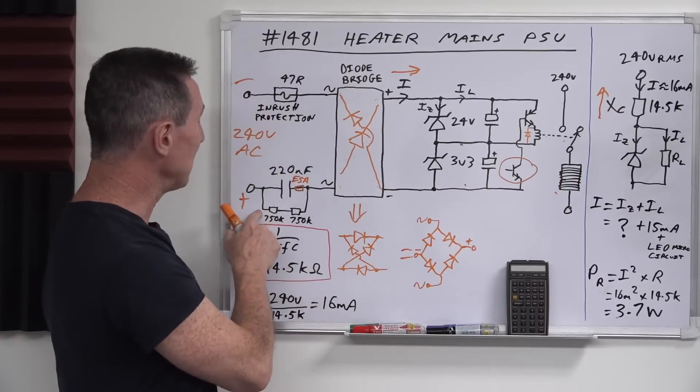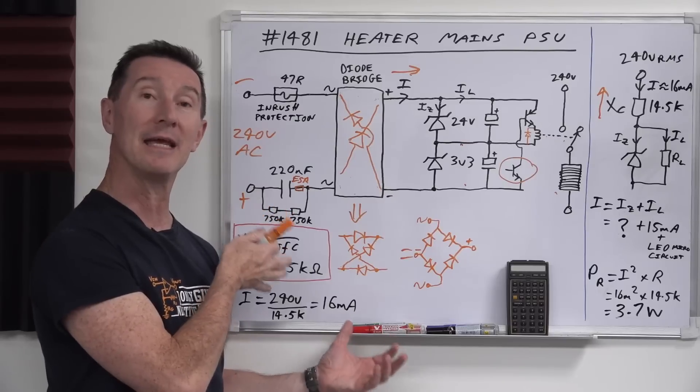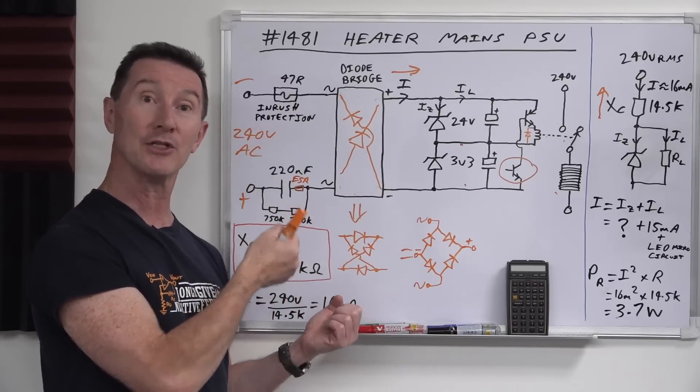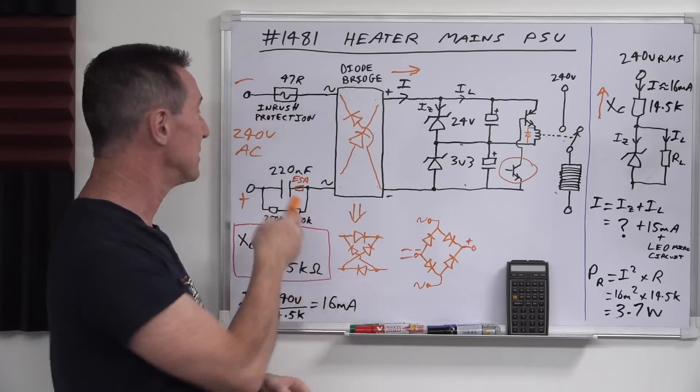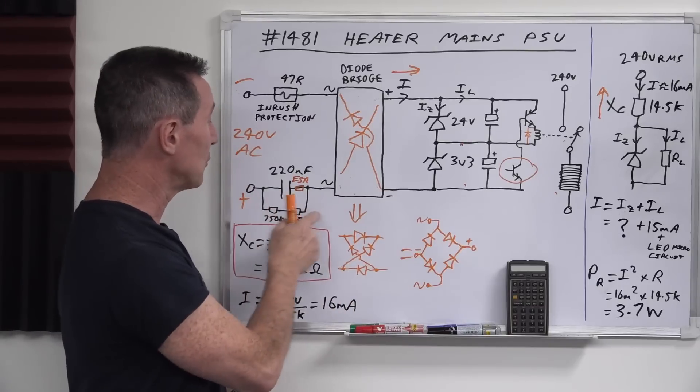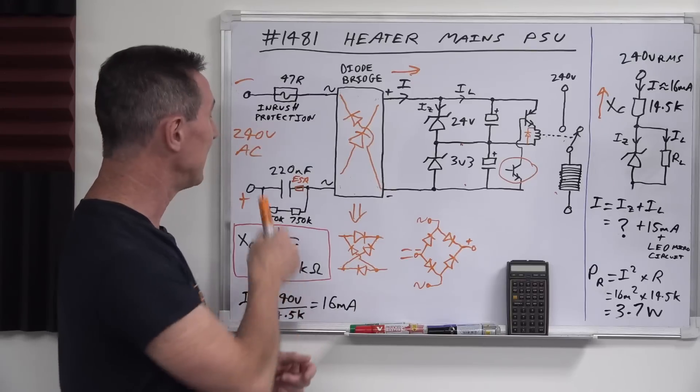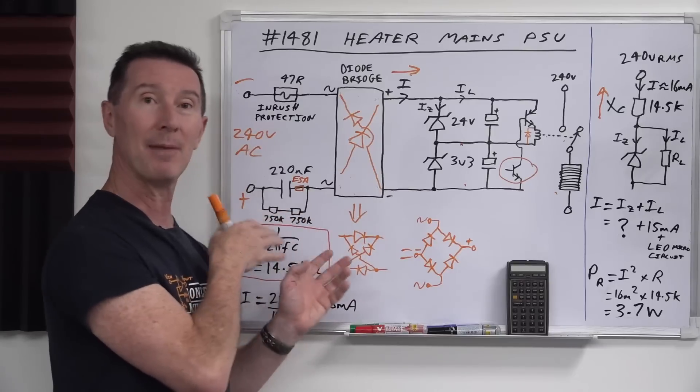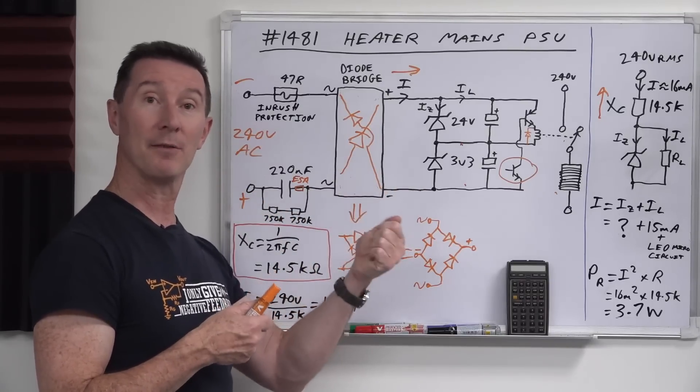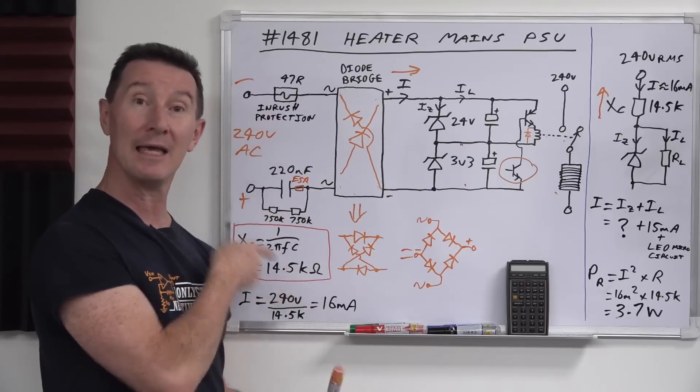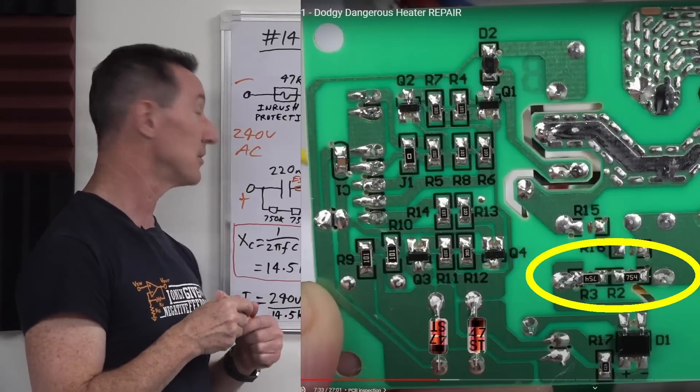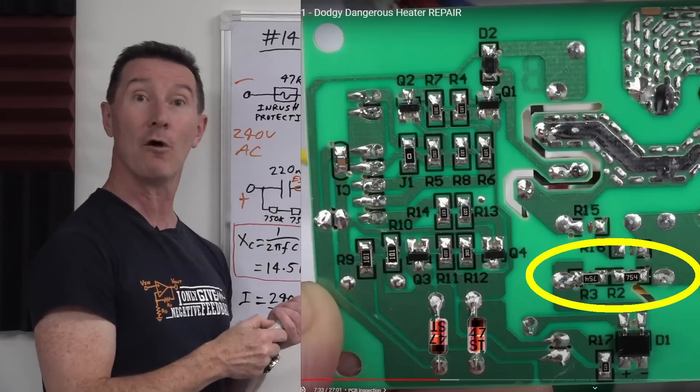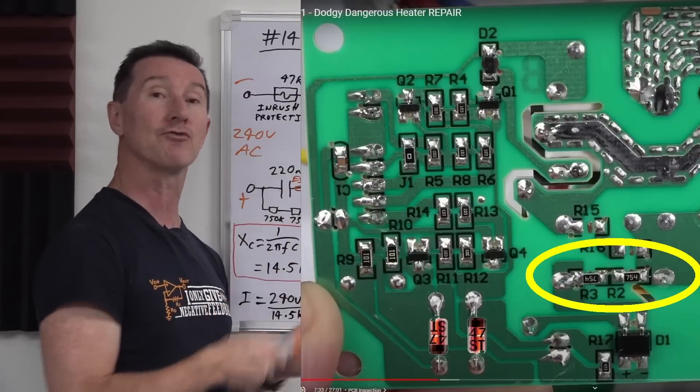And we almost forgot about the bleeder resistors across the 220 nanofarad capacitor here. This is for safety. So, when you pull the thing out, this capacitor could be charged up. You pull it out of the outlet, and you don't want to touch the pins, because then you could get a zappy. So, you've got two high-value resistors, 750k each, and so 1.5 meg total across the 220, and that just bleeds the charge off that capacitor. So, then the user, if they accidentally touch the mains pins, they're not going to get a zap from it. And the reason that they use two resistors in series physically here on the board, you can actually see the two there, is that the SMD resistors that they're using, they're only rated for about 200 volts each. So, they have to put two in series to get the voltage rating required.